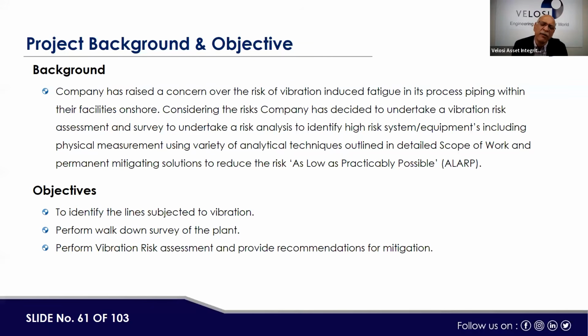Let me share one example from a project, 10 to 15 years ago, where fire water was coming from a jetty to the refinery area. We started the pumping, but the fire water line, which was supposed to carry the water from the jetty, was not properly anchored at various locations. The whole pipe rack was vibrating. The corrective action we took at that time was to put anchor supports and guides wherever required, and then the problem was solved.